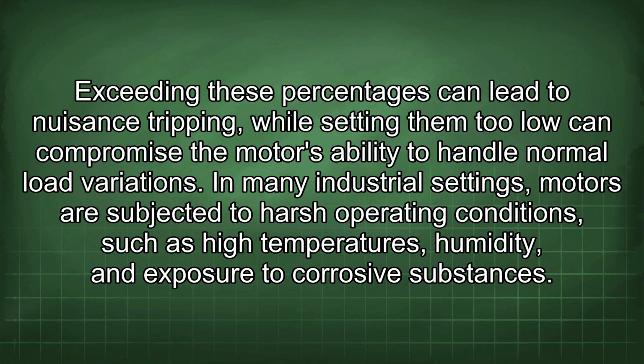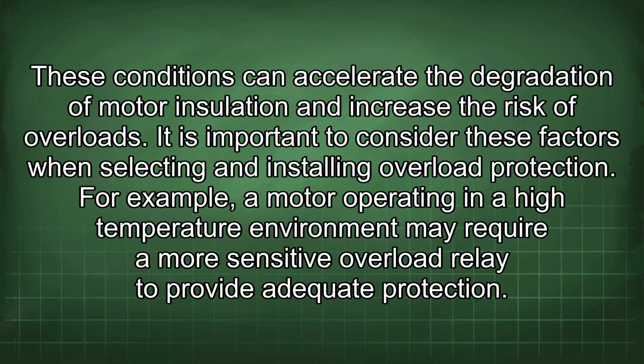normal load variations. In many industrial settings, motors are subjected to harsh operating conditions such as high temperatures, humidity, and exposure to corrosive substances. These conditions can accelerate the degradation of motor insulation and increase the risk of overloads. It is important to consider these factors when selecting and installing overload protection. For example, a motor operating in a high-temperature environment may require a more sensitive overload relay to provide adequate protection.